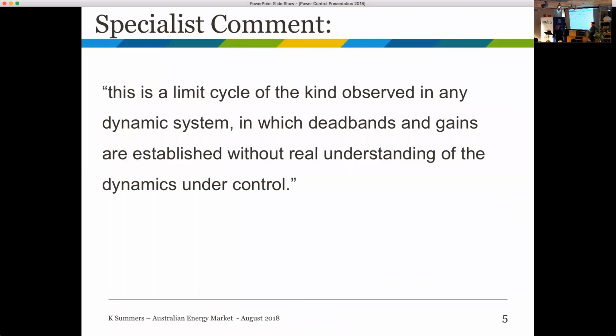Guess what, that could be below 47 hertz, and in that case, lights out, right? So please, when you're contemplating inertia, you must understand that the mechanical response into the machine to arrest the slowing down that's happening because we're sucking energy out of it physically - we have to do something. It's no point getting somebody else to do it somewhere if this machine is the biggest machine on the power system, because it's irresponsible of that machine not to do something if it wants to keep the lights on.